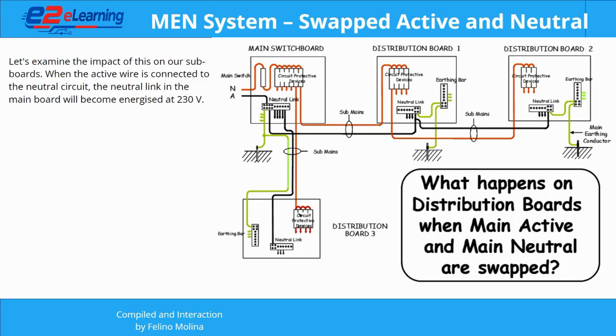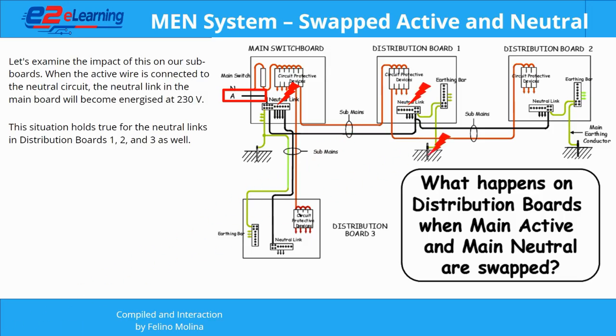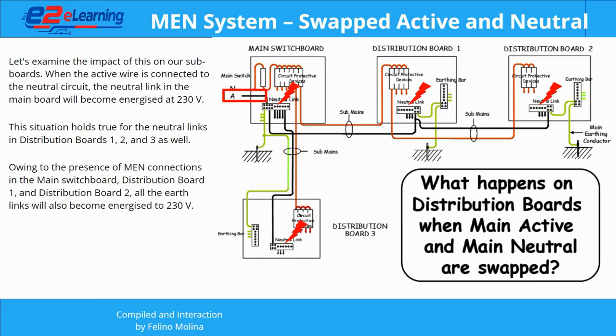Let's examine the impact of this on our subboards. When the active wire is connected to the neutral circuit, the neutral link in the main board will become energized at 230 volts. This situation holds true for the neutral links in distribution boards 1, 2, and 3 as well. Owing to the presence of MEN connections in the main switchboard, distribution board 1, and distribution board 2, all the earth links will also become energized to 230 volts.